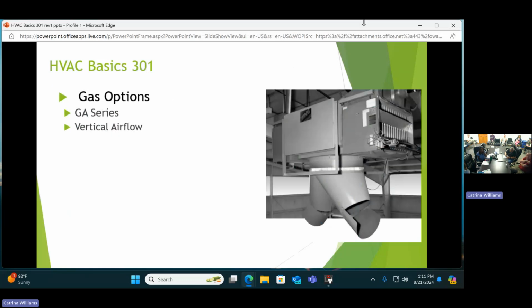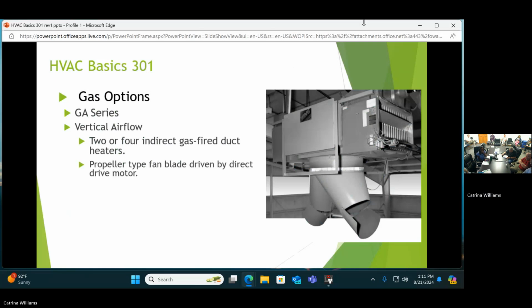So the GA is going to look like this. You've got an air handler up there, vertical airflow. And we're using multiple duct furnaces that we get from our sister company, Sterling, that mount on there to provide the heat. 2 or 4 furnaces in there. Propeller fan, it's a direct drive motor, so we're not worried about having to get up there in the rafters and adjust belts or change belts. And these are available with either 4 fixed, 4 revolving, or again, the Varijet. So we can take a gas unit and make it a combination door and space heater outlet by using this Varijet design on this model. Again, it makes it quite versatile.